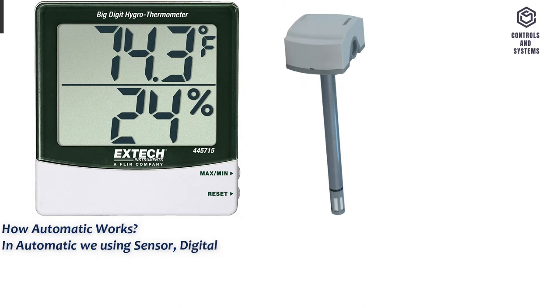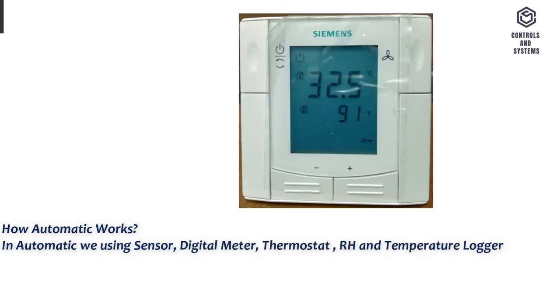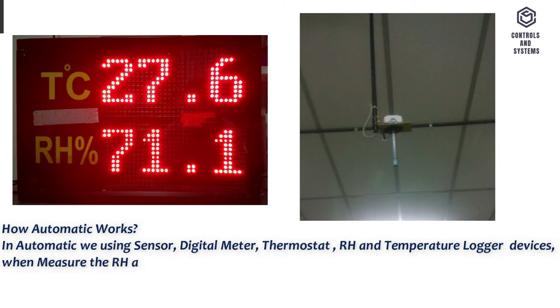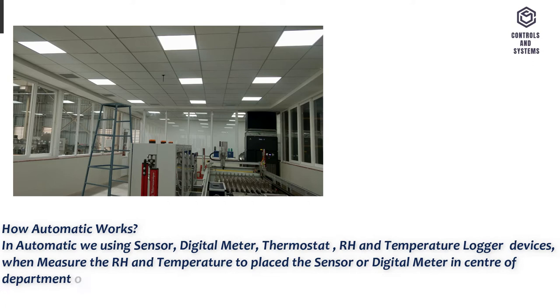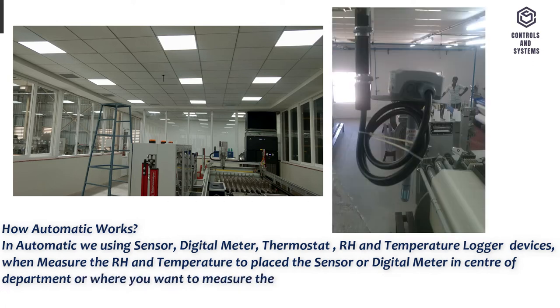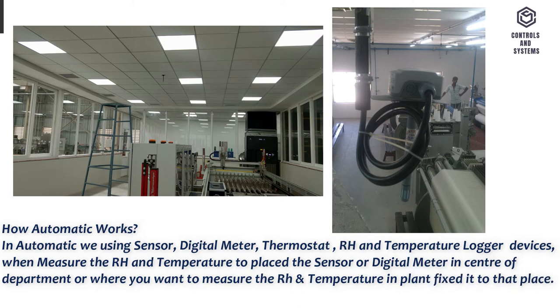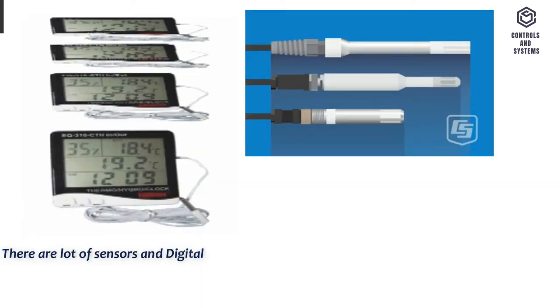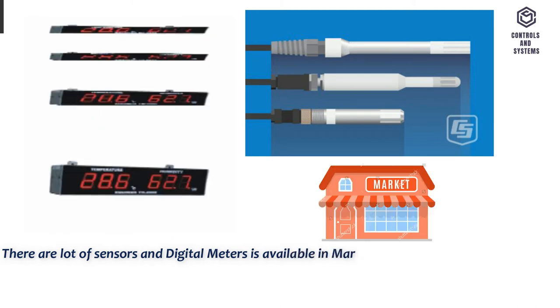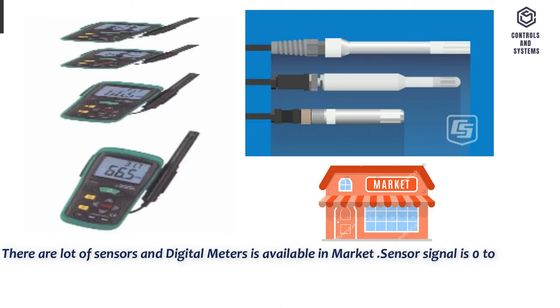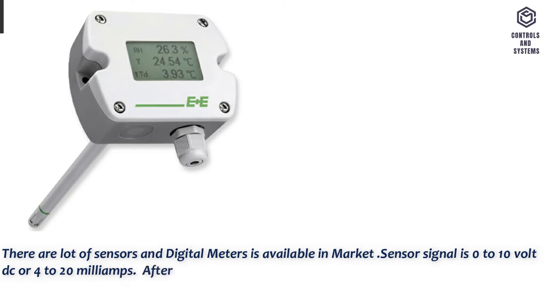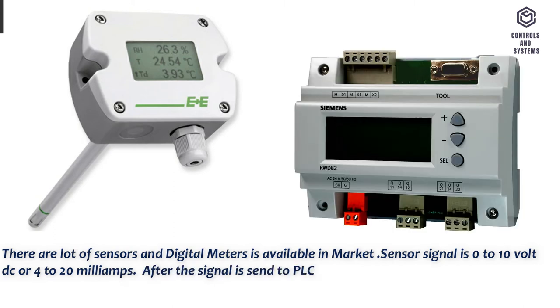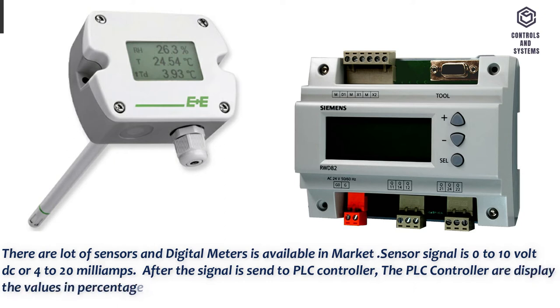In automatic we use sensor, digital meter, thermostat, RH and temperature logger devices. When measuring the RH and temperature, place the sensor or digital meter in center of department or where you want to measure, and fix it to that place. There are lot of sensors and digital meters available in market. Sensor signal is 0 to 10 volt DC or 4 to 20 milliamps. After the signal is sent to PLC controller, the PLC controller displays the values in percentage.